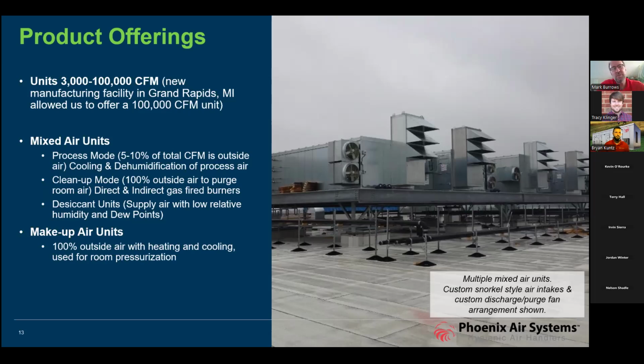If it's a case where there's a sanitation problem, where that room's a big fog bank, by all means, then we'll use that 3-minute air change. Just take a makeup air unit, no cooling required. In the summertime, we're bringing raw ambient air in to flush the room out. If we're bringing 50,000 CFM in, we're taking that out as well. If it's cold outside, of course, we don't want to bring in 0-degree air into a cleanup situation. We'll heat the air to 80–85 degrees and then discharge that in the room. And again, that dry air will then pick up the moisture and take it right out to atmosphere.